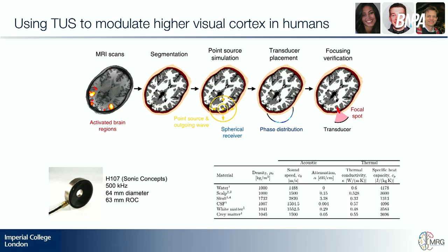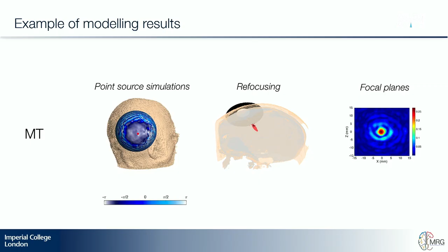We then segmented out their brain, and using the segmented brain with all the different types of tissue, skull and CSF and water, we were able to create computer models whereby we could determine exactly where we needed to place our transducer in order to hit that spot and to deliver safe amounts, what we hope are safe amounts, of energy to the required site. Okay? And the way you do that is you imagine you've got your source here inside transmitting ultrasound out. You collect what is out there where you might place your transducer, and you measure the phase distribution and the amplitude distribution there, and then you reverse model that to make sure it's hitting the right place. So this is our phase distribution as we imagine we're at MT, and you can see there's an area here where the phase is relatively homogeneous, and when we refocus we get this nice cigar shape, again with about 5 millimeters across.